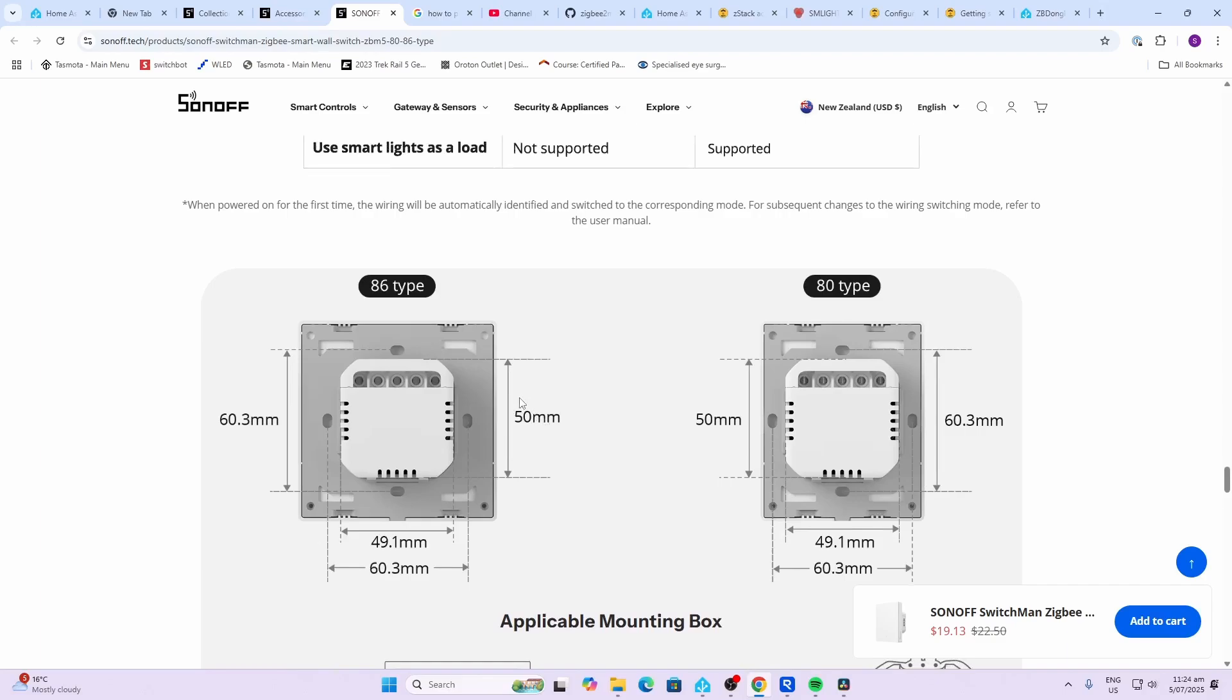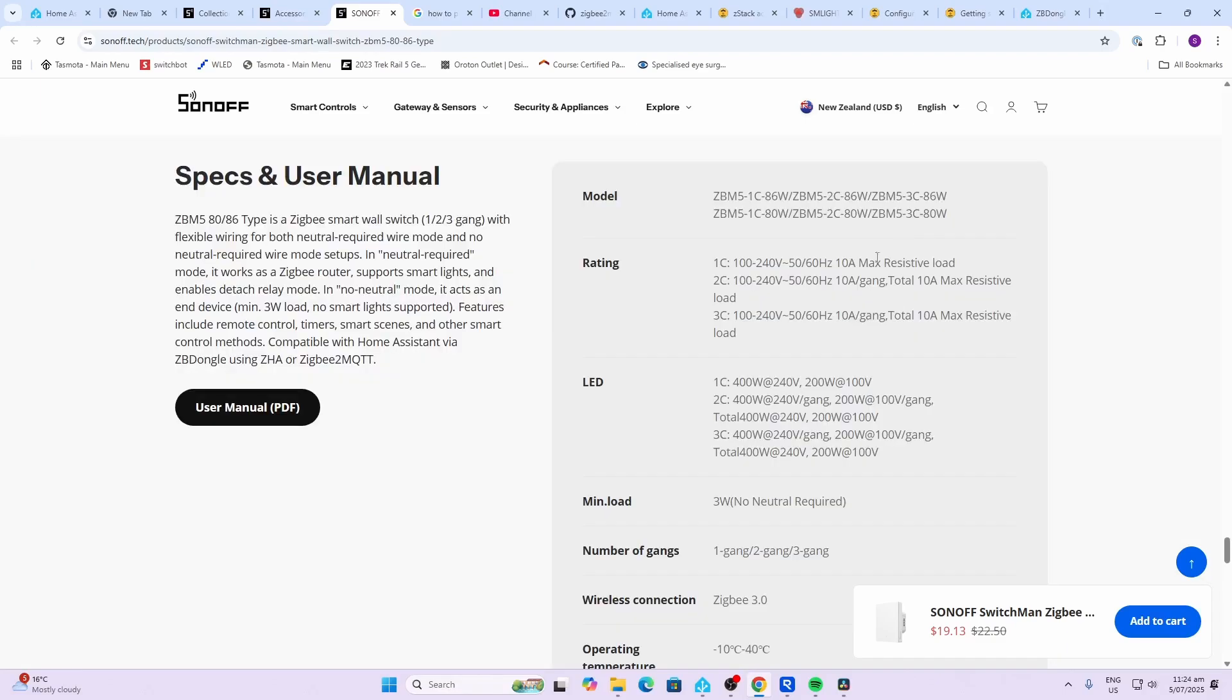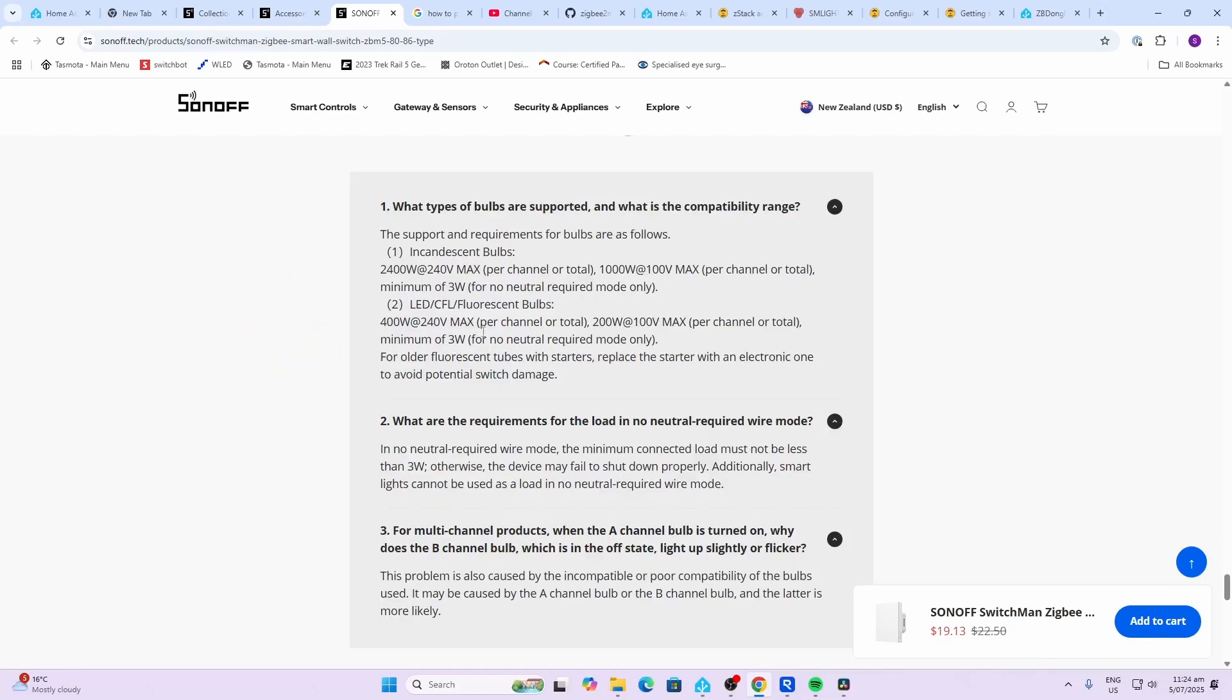Comes in two form factors, either the 86 type or the 80 type. The total maximum resistive load is 10 amps. If you're using fluorescent bulbs, you need to use an electronic starter rather than the old fluorescent starters, which can damage electronic switches.